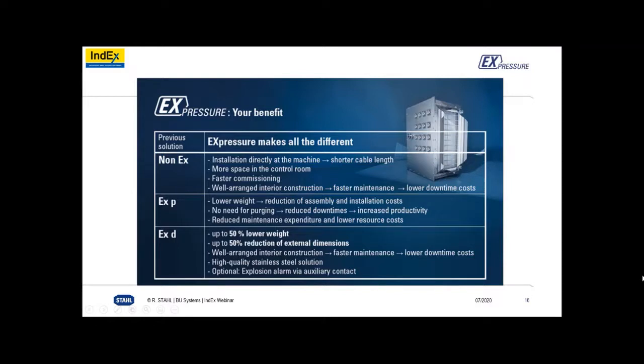Yeah. As I told, with non-EX, you have one installation directly at the machine. That means you have shorter cable lengths. You don't need to come from the safe area into the EX area with many hundred meters of cable length. You have more space in the control room because you have one cabinet, one enclosure, and it can be useful in the case of a brownfield installation. You have faster commissioning because you need less personnel for setup and installation, and this also reduces your logistic time and installation time.